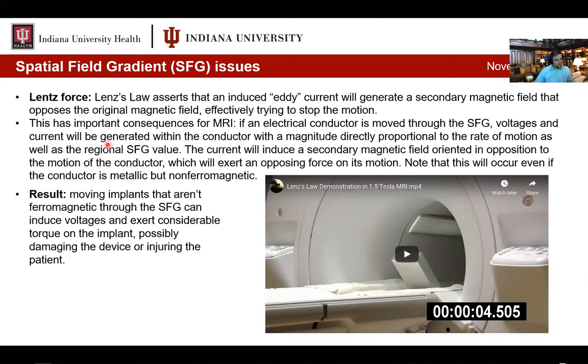That gets us back to not allowing the patient to sit up. When they sit up, they get closer to the edges of the magnet where the spatial field gradient magnitude is highest. When they move fast, the eddy currents are in magnitude proportional to their rate of motion. So these are the reasons physically that you don't want them to sit up, and that you do want to keep them lying down and move straight out as slowly as possible if you find out someone has an implant, or if you know someone has an implant, they're going in and you want to protect them from any potential harm, even though you've approved the implant to go in.